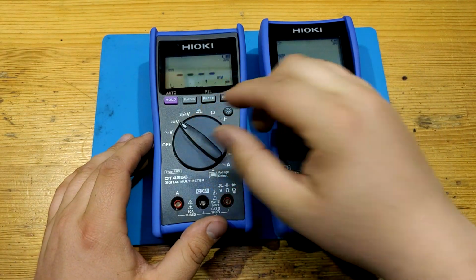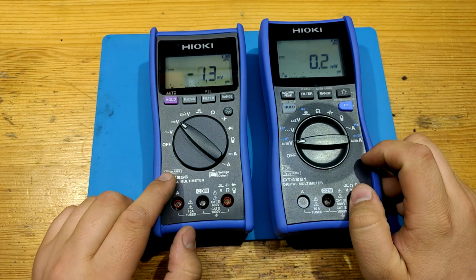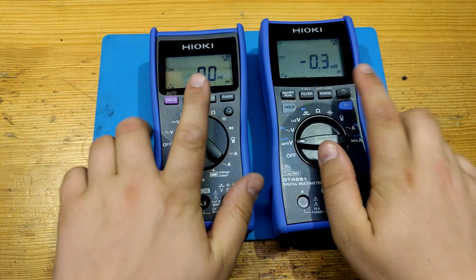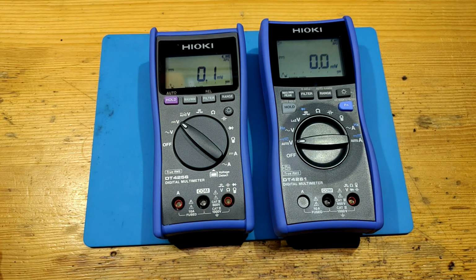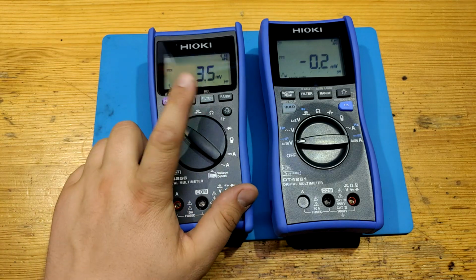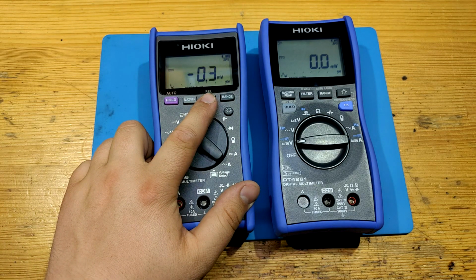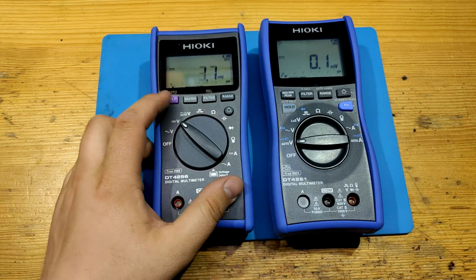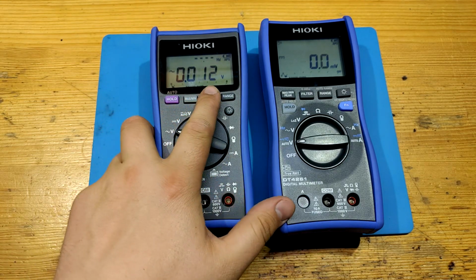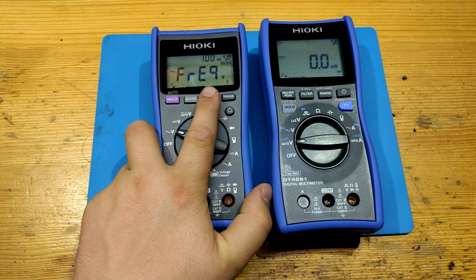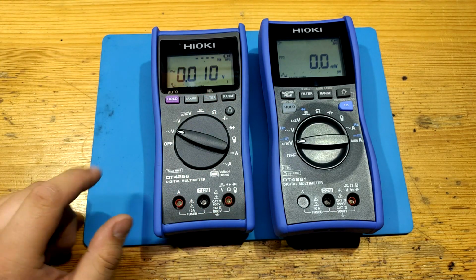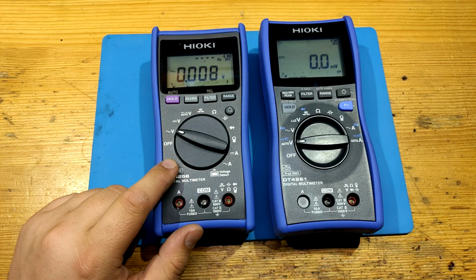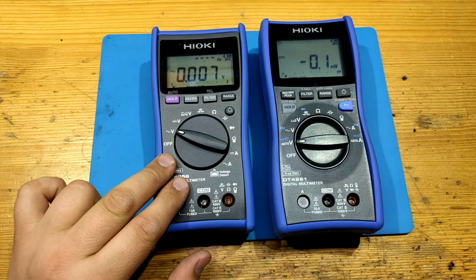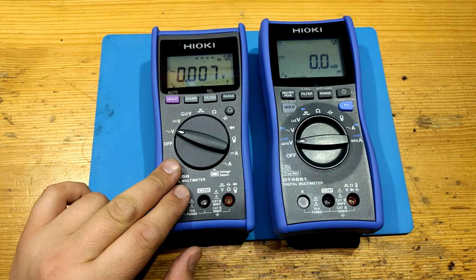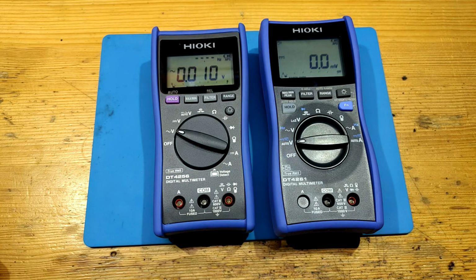Regarding DC millivolts, both multimeters have the most sensitive resolution down to 0.1 millivolts, so you cannot measure below 100 microvolts. Now a little surprise. Filter. Low pass filter. Both DMMs have a switchable low pass filter: let's just use AC, off, 100 Hz and 500 Hz and off. When off, they are limited by the true RMS ADC, 4256 being able to measure up to 1.5 kHz to keep within specs, and 4261 up to 235 kHz.